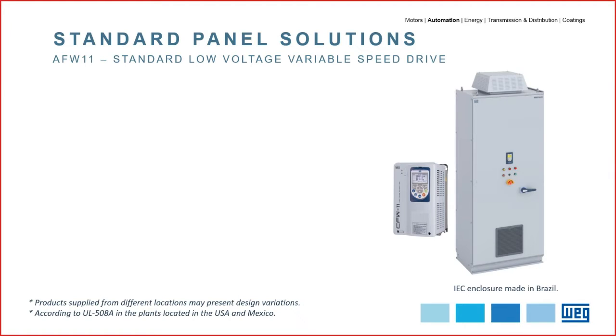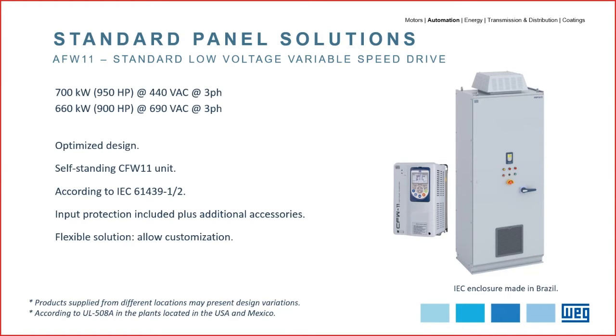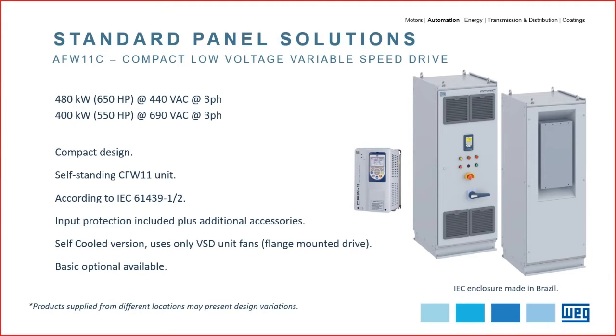First, the AFW11. This is WEG's main product line for VSD panels. This product line allows a sort of optionals, like additional IOs, communication, and temperature monitoring modules. With this product line, we can go up to 700 kilowatts at 440 volts and 660 kilowatts at 690 volts. The next one is the AFW11C. This product line is similar to the AFW11, but it has a better cost benefit when compared to the AFW11. But on the other hand, this product has basic optionals available. Once this is not provided with forced ventilation, the output power is limited to 480 kilowatts and 400 kilowatts at 440 or 690 volts.